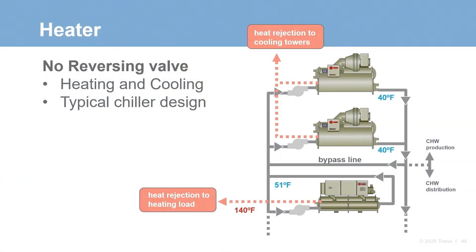Next is the heater. A heater is the same machine as a heat recovery chiller, but is applied with heating being its primary function and chilled water is the useful byproduct. Here we see the heater piped in a sidecar arrangement. These units control to a heating water set point and get what they get on the chilled water side, as the cold water is being sent to the return of the main chiller plant. Common uses are similar to heat recovery, but the load dictates which application is appropriate.